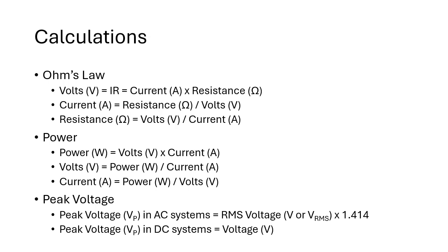One that's less likely to come up with power supplies is peak voltage. In AC systems, we take the RMS voltage, or the root mean square voltage, and you multiply that by 1.414. So for example, in a 240 volt system, if you measure the system, you'd see 240 volts using the multimeter, but the actual maximum voltage is 1.414 times the RMS voltage. Not particularly of use because you don't really worry what the peak voltage is, but I do recall it coming up in the past when I was specifying particular overvoltage protection devices.